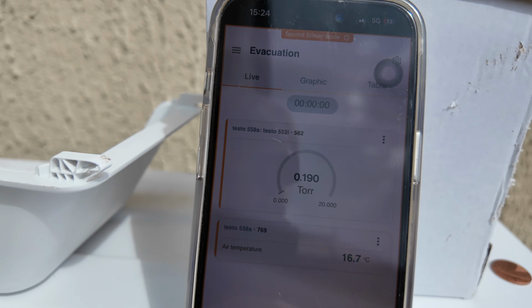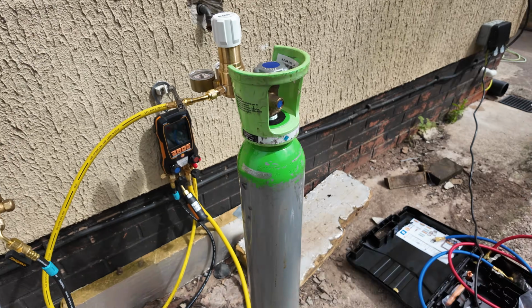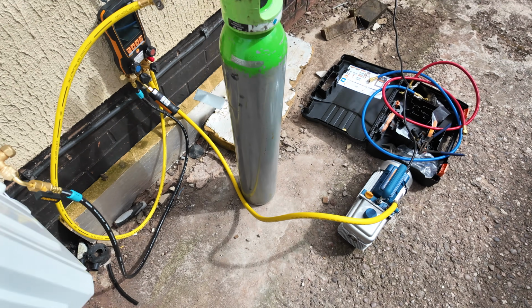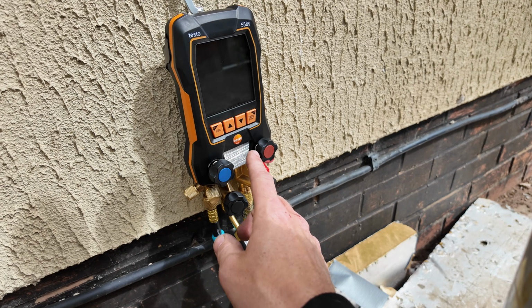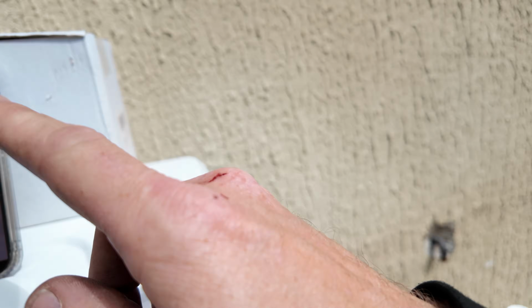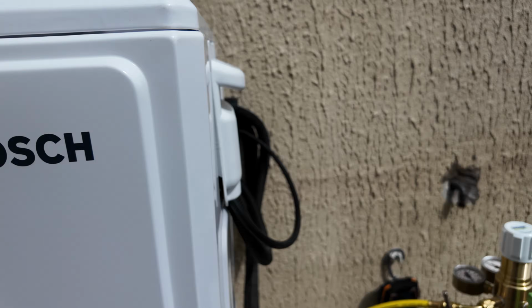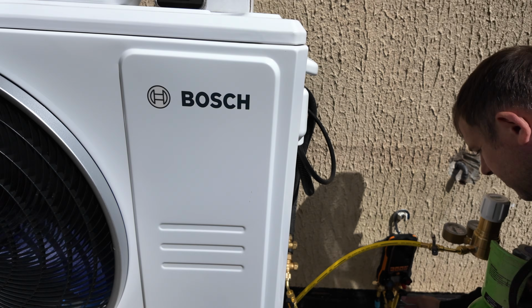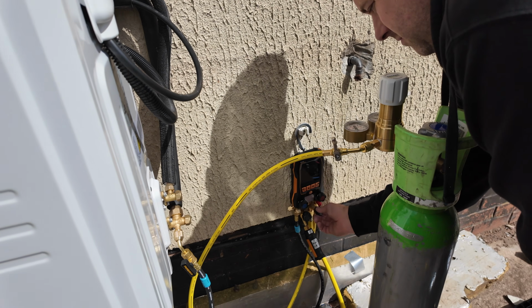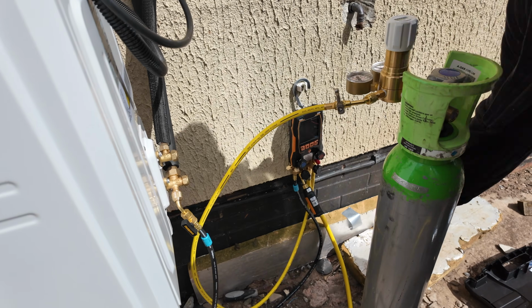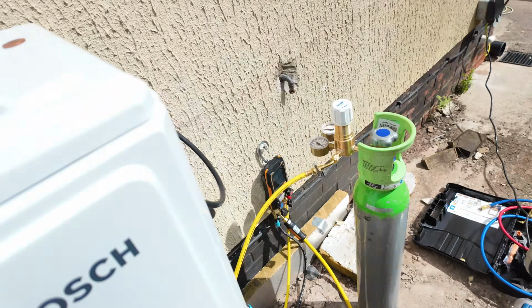That's low enough now. Before you turn that off, make sure you lock it off, because if you don't, that will just shoot up and you'll lose your vacuum. You've got to make sure you shut it off before you turn it off. So that now should be ready to shut off. Chris is just going to shut off the gauge there and then shut off the pump. You don't want that jumping right up. It will go up.